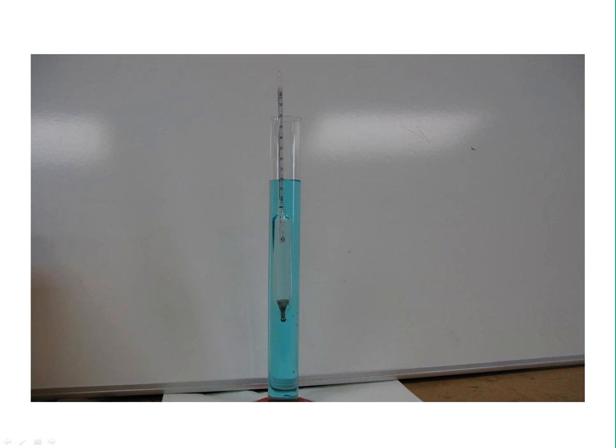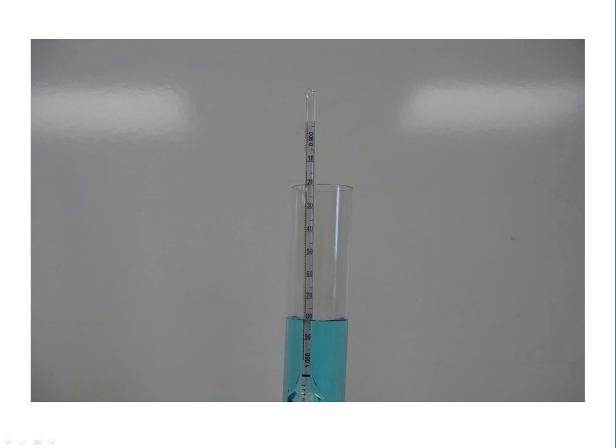It does not necessarily need to be clear. You can use a piece of 1-inch PVC, for example. It needs to be at least 12 inches long, again, so it'll freely float. If it's a piece of PVC, for example, you're going to need to fully fill that cylinder so that when you drop your hydrometer in there, it will displace fluid, and you will then be able to read the scale at the fluid line. In this example, we have an alcohol hydrometer.